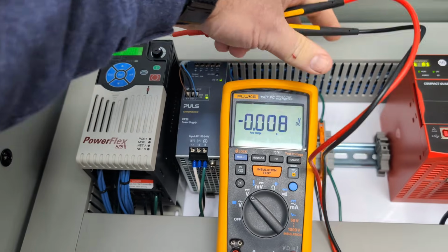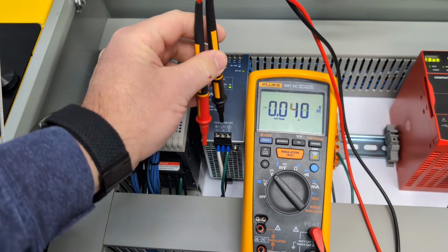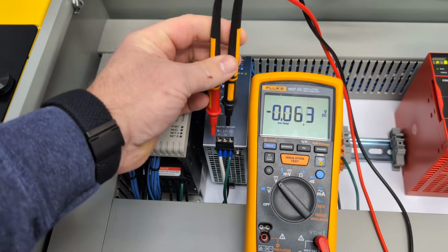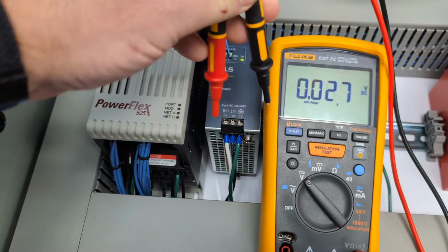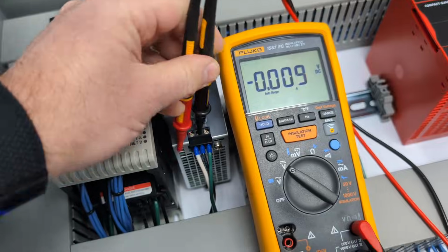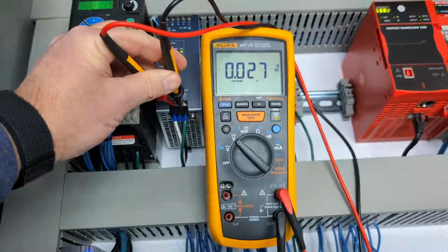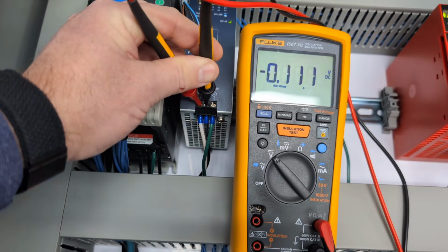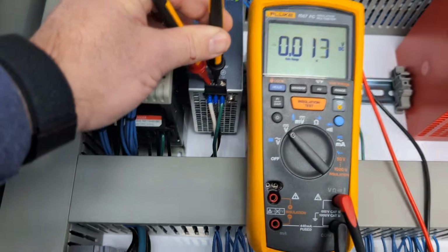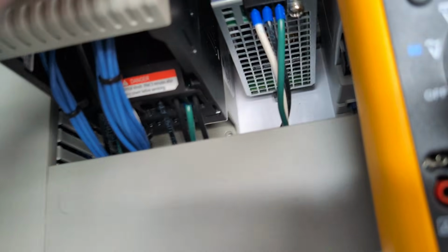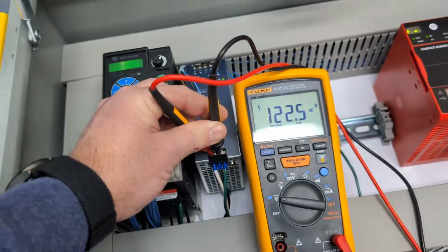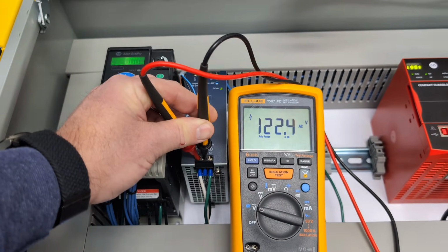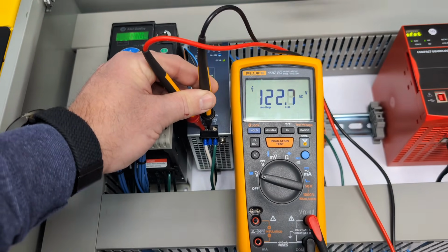Well, the next thing you would check up here, and I will say nearly always people, even experienced people, gosh, I'm going to hurt myself sitting here trying to do this. They don't think to change their leads. So now we had no power at the top of our power supply. We have no power here, and we feel there's no power on these wires here. But if I reach down here, and y'all get busy a second, because apparently I can't hold everything, and I switch it to AC, we realize we do have power there. So that's the purpose of this lesson.